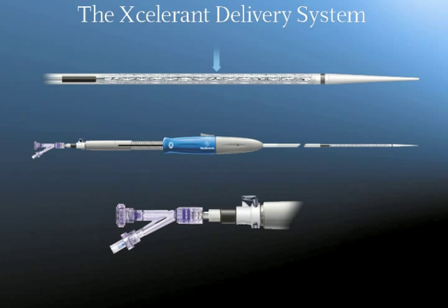The stent graft is constrained inside the Xcelerant Delivery Catheter. The Xcelerant Delivery System consists of a single-use, disposable catheter with an integrated handle to provide controlled deployment, a flexible catheter assembly compatible with .035-inch guide wire, runners that reduce friction between the AneuRx stent graft and the graft cover, an atraumatic, radiopaque, tapered tip to facilitate tracking through tortuous vessels, a radiopaque marker band at the distal end of the stent graft, and a marker on the end of the graft cover to aid in fluoroscopic visualization.